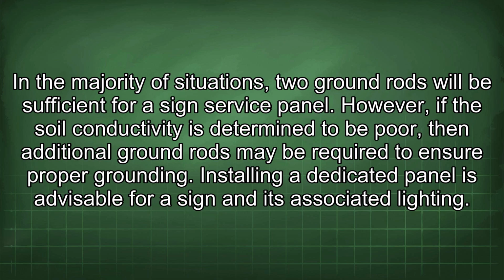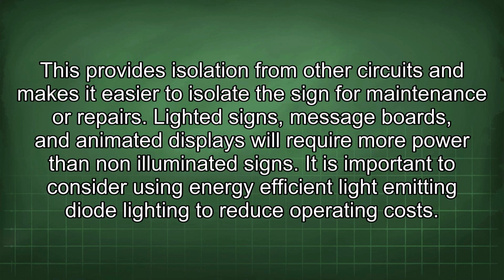However, if the soil conductivity is determined to be poor, then additional ground rods may be required to ensure proper grounding. Installing a dedicated panel is advisable for a sign and its associated lighting. This provides isolation from other circuits and makes it easier to isolate the sign for maintenance or repairs. Lighted signs, message boards, and animated displays will require more power than non-illuminated signs. It is important to consider using energy-efficient light-emitting diode lighting to reduce operating costs.